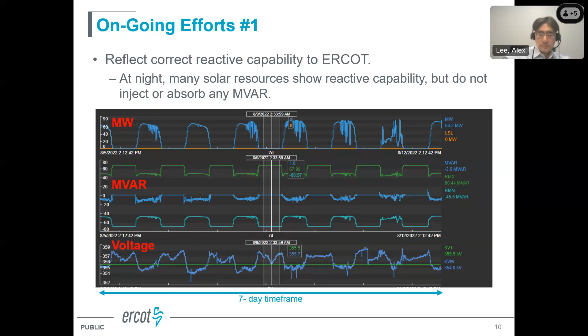In addition, ERCOT is working on a couple of different efforts over the past couple of years. As I mentioned in the second example, oscillation events seem not to be limited to just megavar oscillations at 0 megawatt output. We have also seen quite a bit of megawatt oscillations on IBRs. We have also seen megavar oscillations at non-zero megawatt output. We also saw some simultaneous oscillations on both megawatt and megavar at the same time, as well as other types of oscillations such as sub-synchronous resonance.